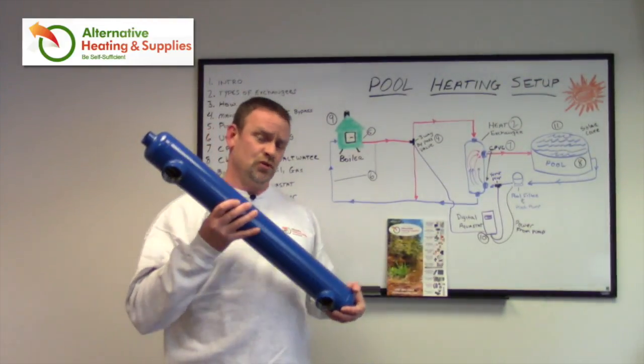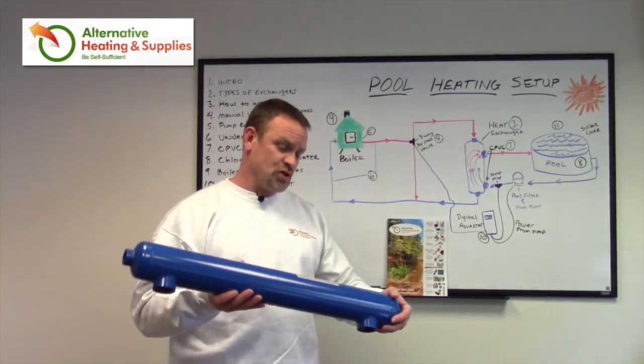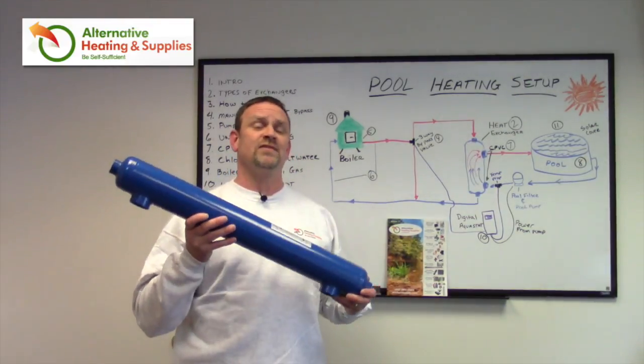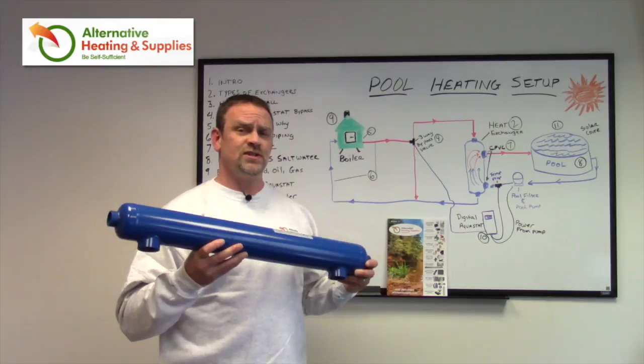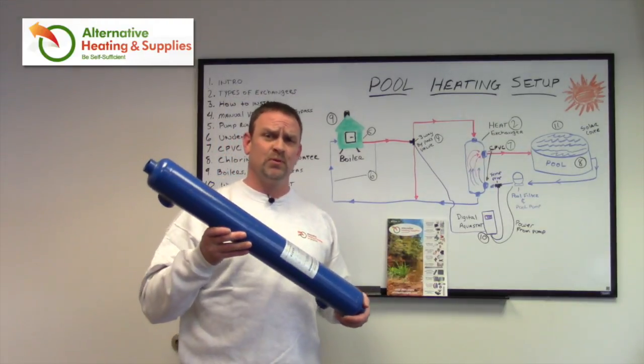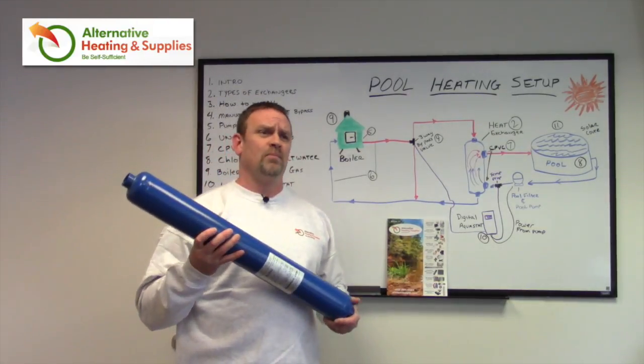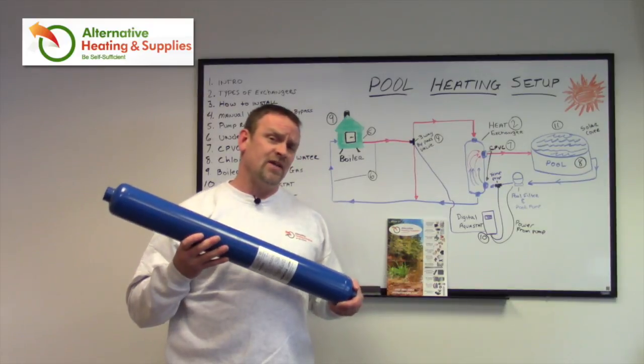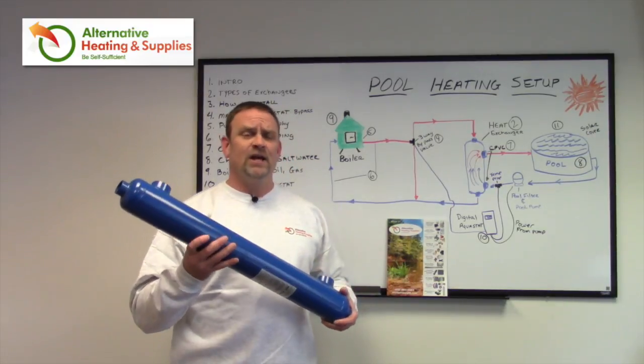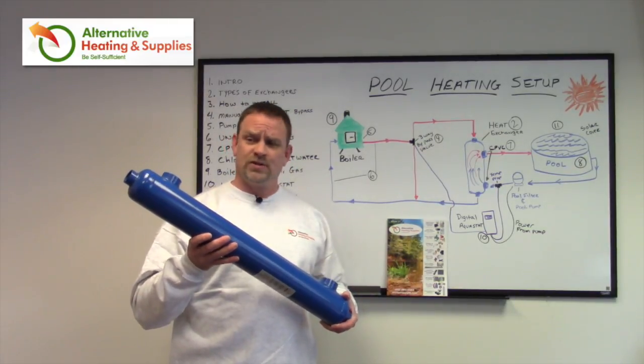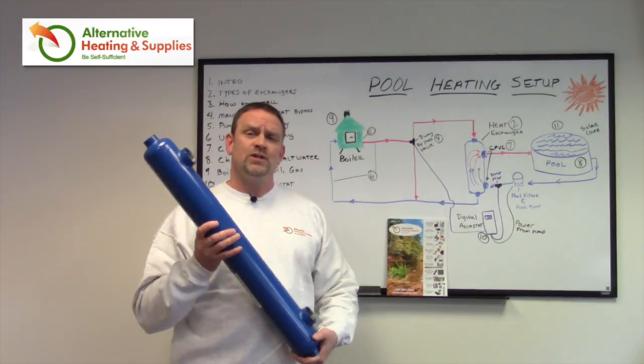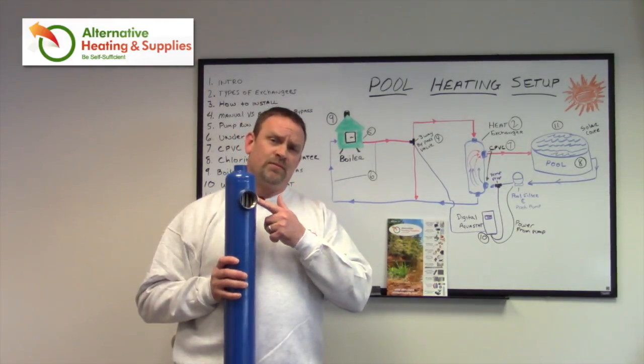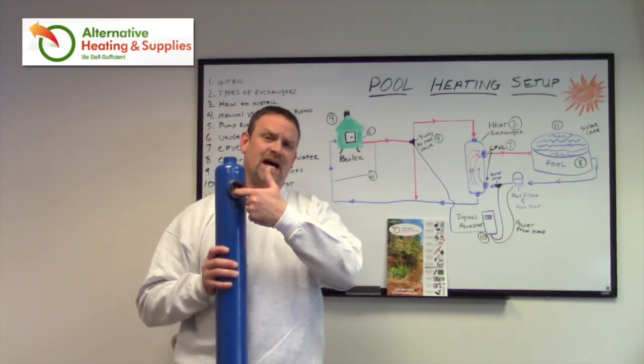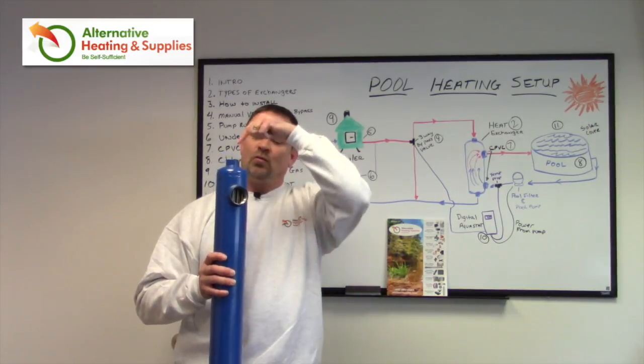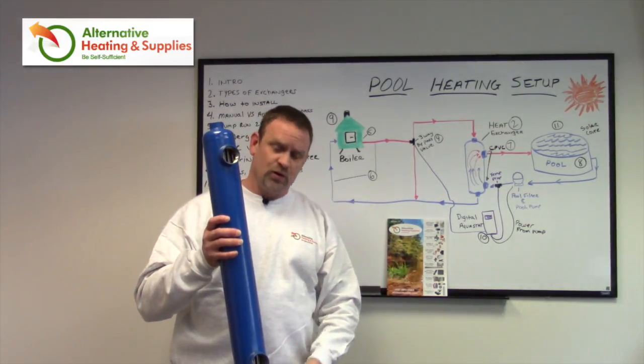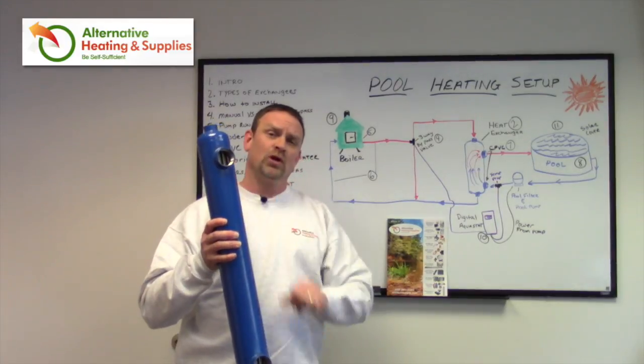This is another tube and shell heat exchanger. This is a much larger one. This is about 370,000 BTUs. This is enough to heat an average size swimming pool, anywhere in the ballpark of 15 to 25,000 gallons. I can help you calculate that, or the website can also help you figure that out. Basically, the water comes into this large port from the pool, and there are tubes inside that the water from the boiler is going through, which separates the pool from the boiler water.